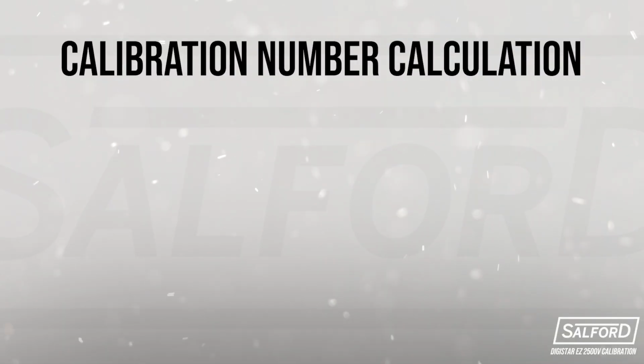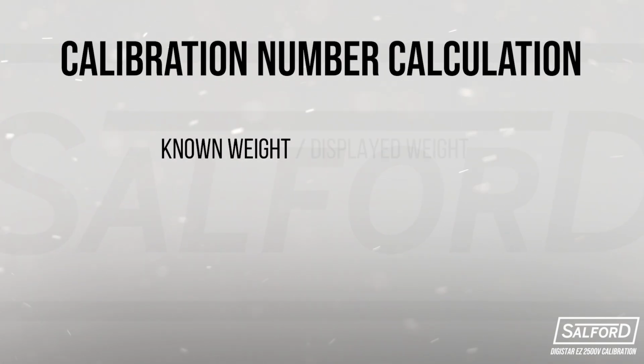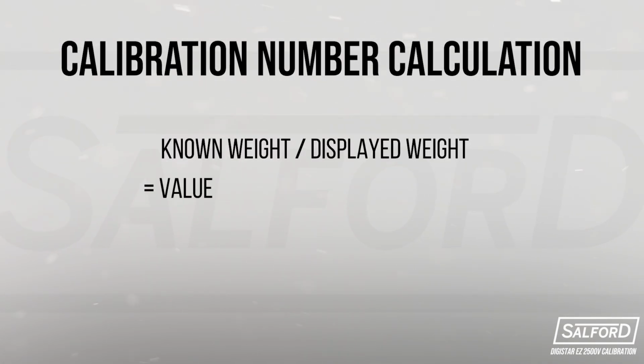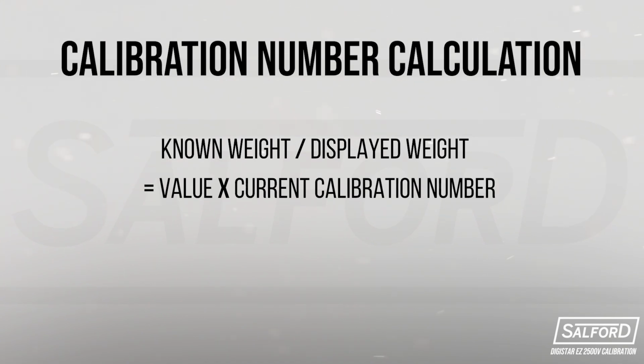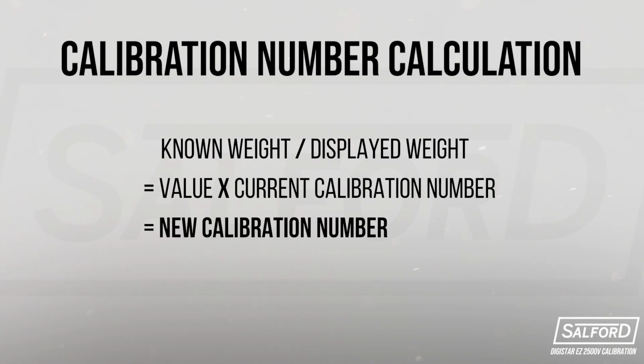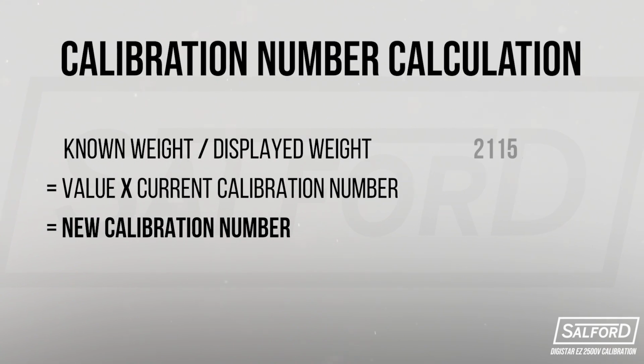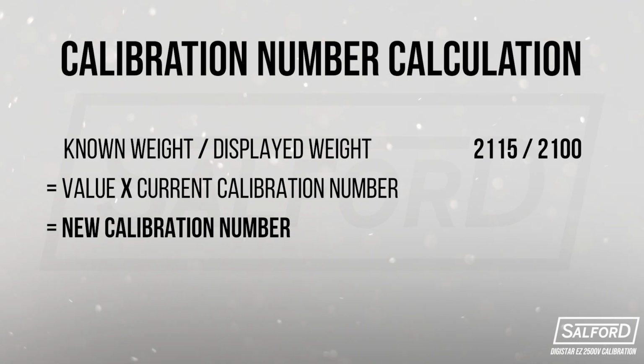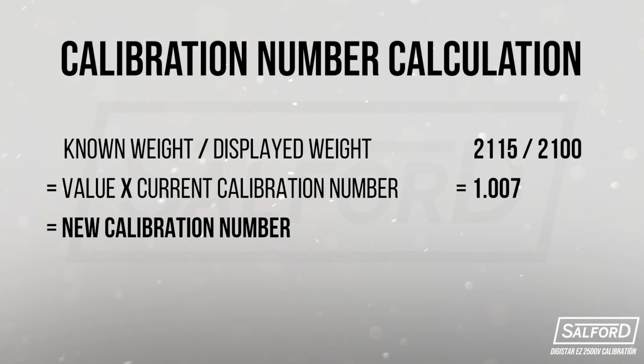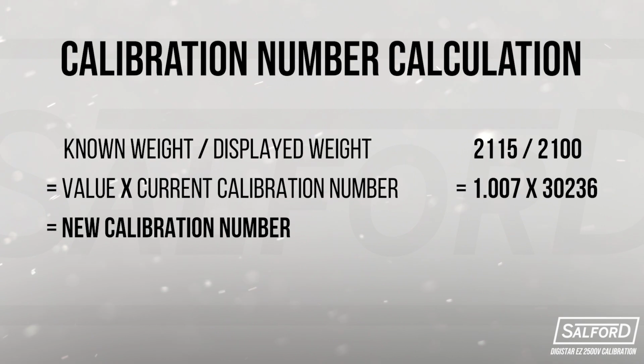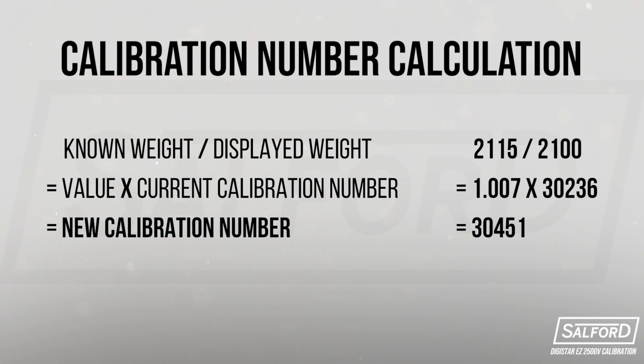To calculate the new calibration number, take the known weight and divide it by the displayed weight, then multiply that value by the current calibration number to determine the new calibration number. In this example, the known weight is 2,115, which we divide by the displayed weight, 2,100. This gives us 1.007, which we then multiply by the current calibration number, 30236, which was set during the initial setup based on the 8 load cells on the machine. This results in the new calibration number 30451.